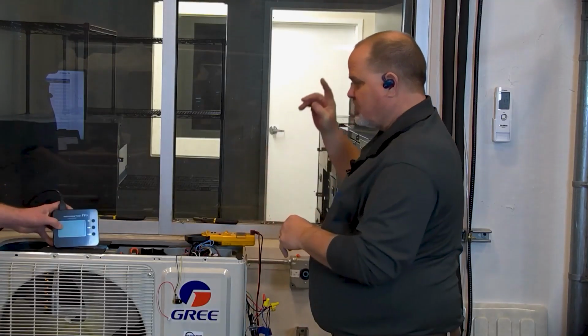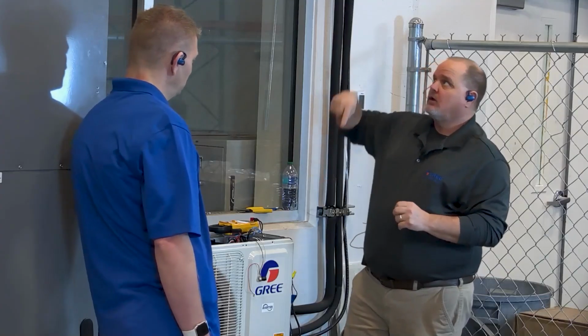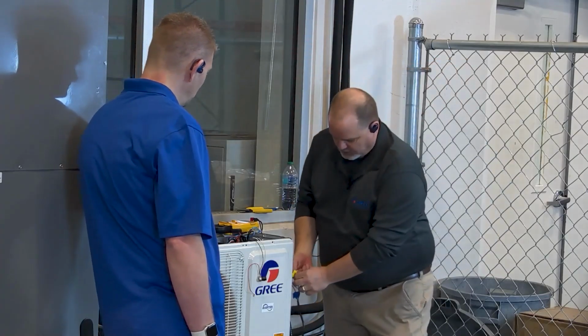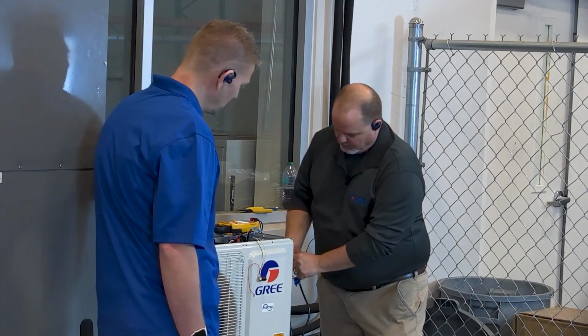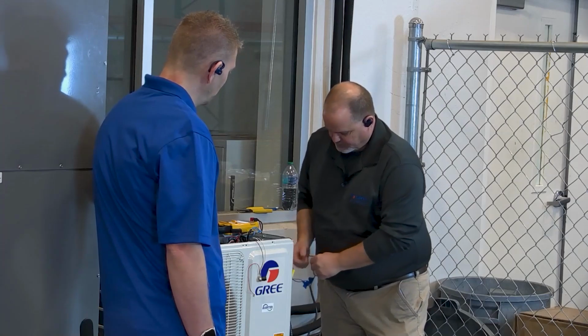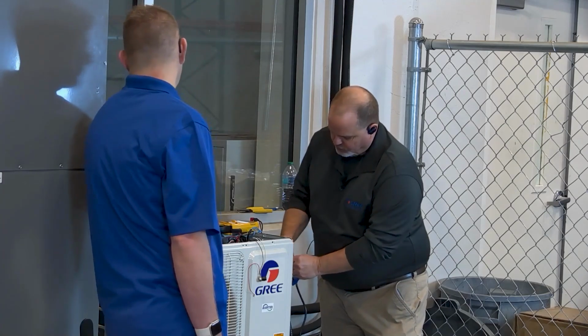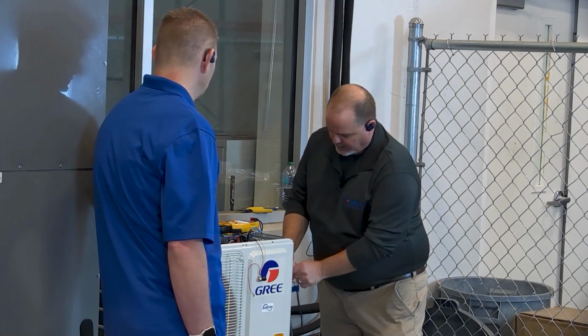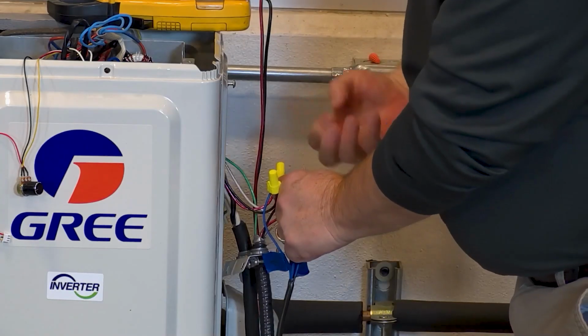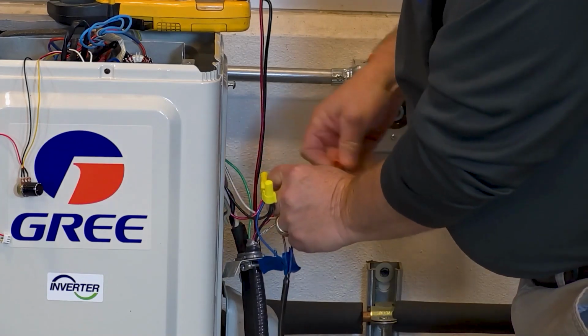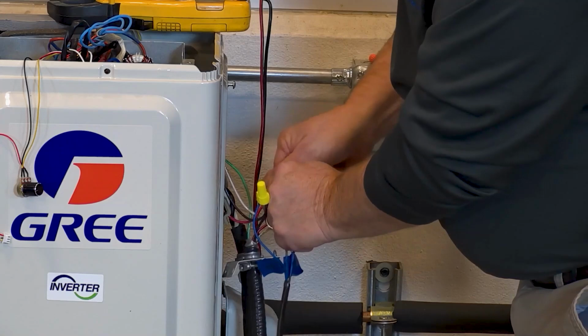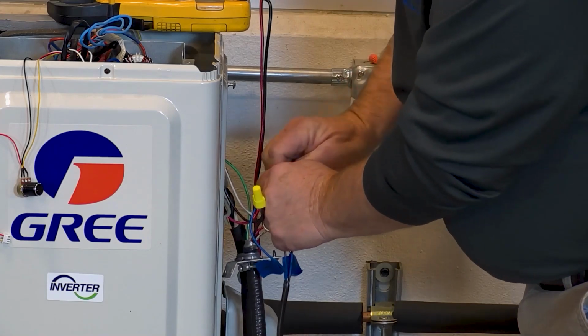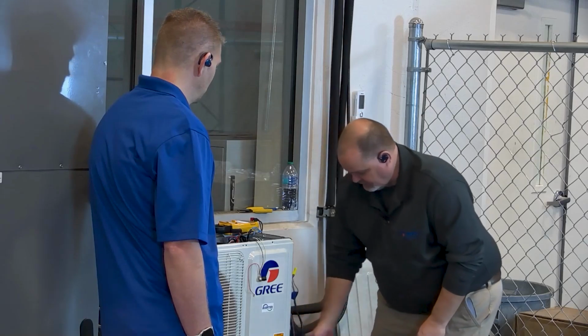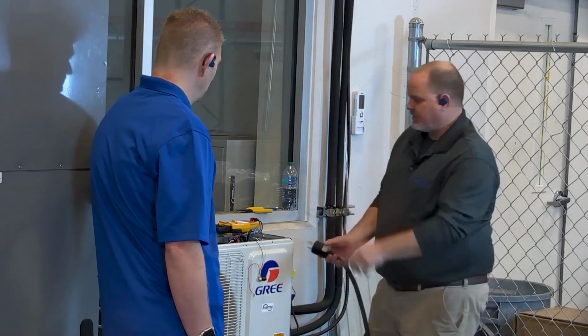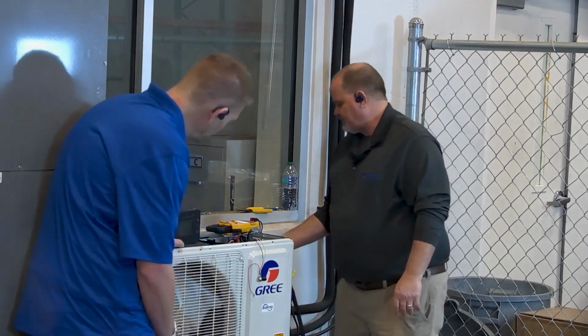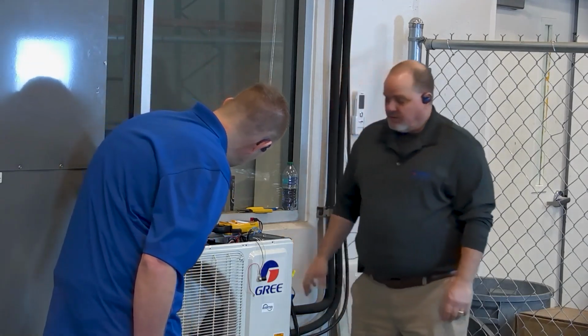So now we're going to simulate the outdoor unit to detect the indoor unit. So all I'm going to do is take the number 2 wire from the service tool and hook it to the 2 wire going inside and not have it hooked to the 2 wire on the outdoor unit. Then we'll power it back up. We should get the screen again. And we can take it the other way around.